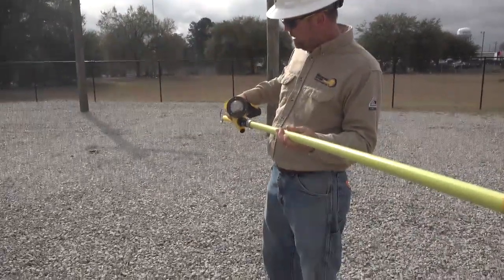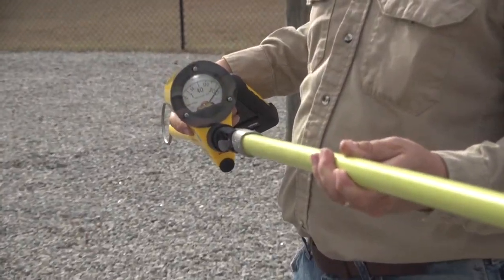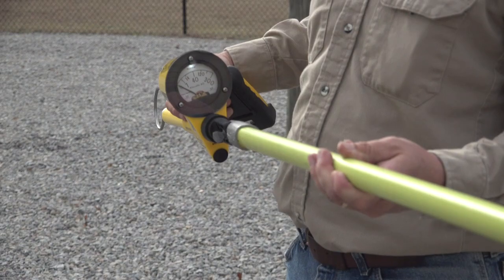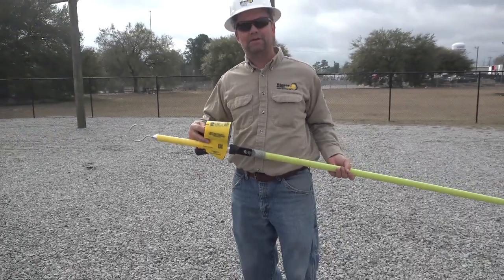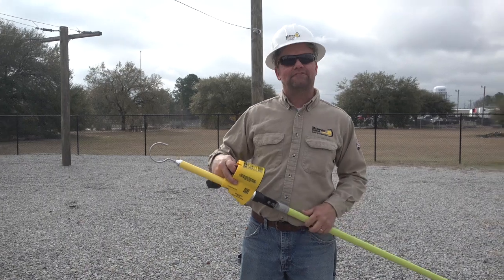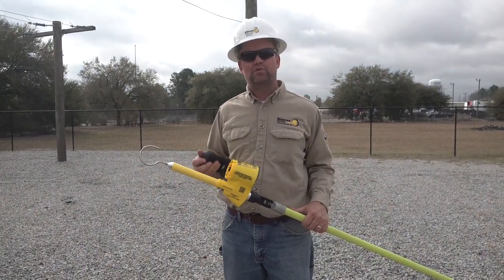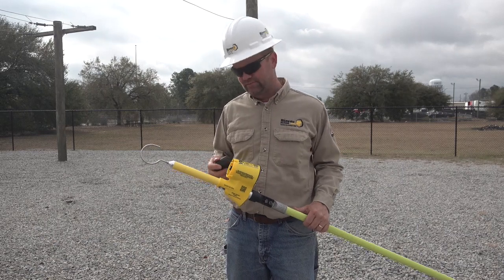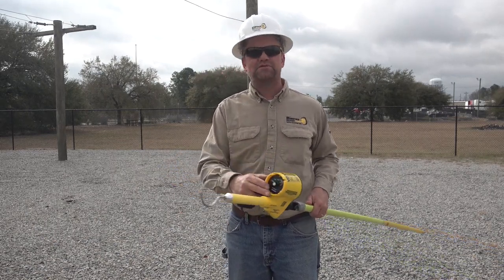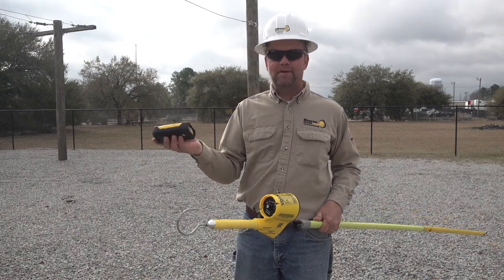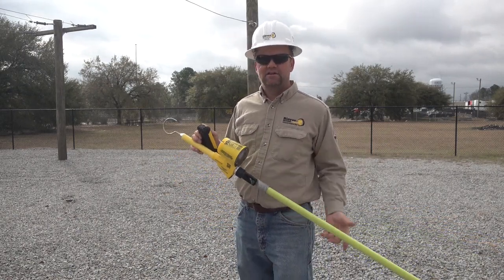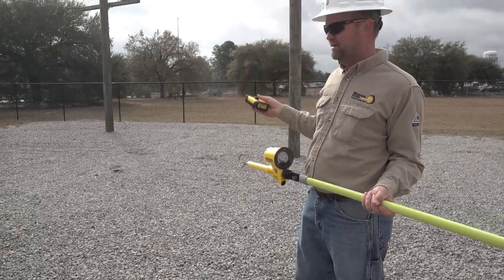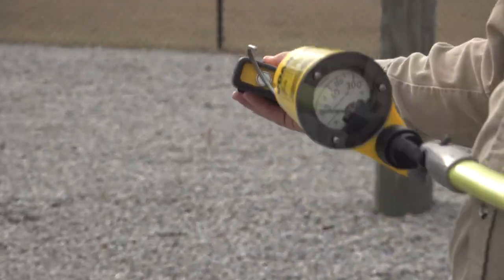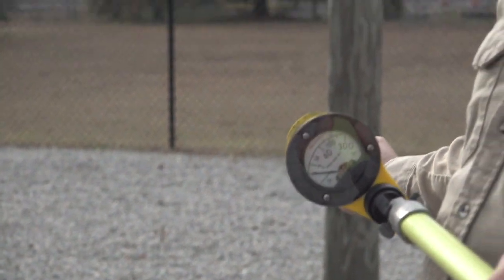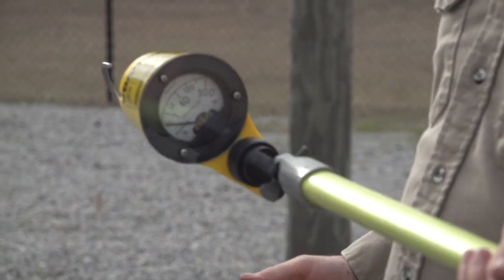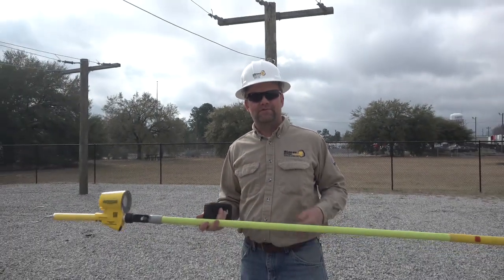I hold it to the test or T position. Make sure I get a full needle deflection or near full needle deflection. Again, if I do not get that, replace the battery. If the battery does not fix that problem, again, we highly recommend you have the tool repaired and or calibrated. If I turn the tool to the first on switch position and again use our handheld power supply and touch the hook probe adapter, which is what I'm going to utilize here today, I should get a needle deflection. Make sure the needle deflects and goes near 0 whenever I remove the handheld power supply.